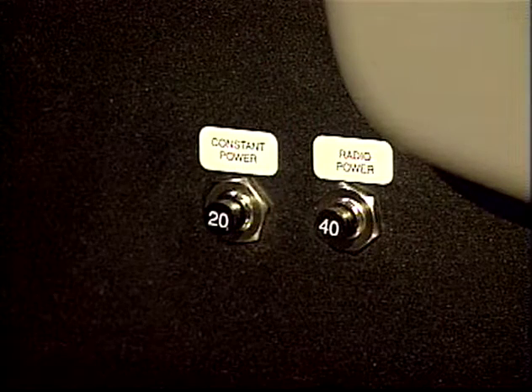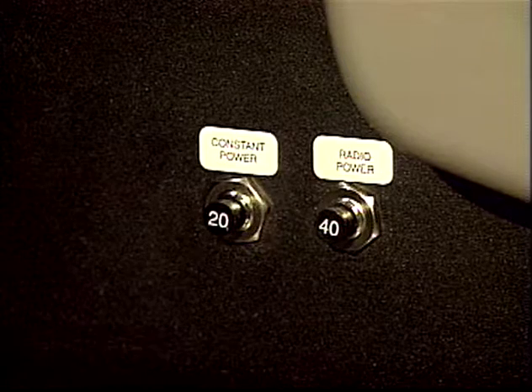Medtec has designed the front console so that not only is it very functional, but it's easy to access for maintenance. Performing maintenance on the front console is only a matter of releasing the rubber pull straps, separating the electrical pin blocks, disconnecting the console from the ambulance, troubleshooting, repairing, and reinstalling in reverse order. When installed, the console's design provides an appealing finish to the interior of the cab. Located in the driver's seat base is one 20-amp circuit breaker and one 40-amp circuit breaker. The design of these circuit breakers allows you to pull out the center reset button to de-energize the circuit.